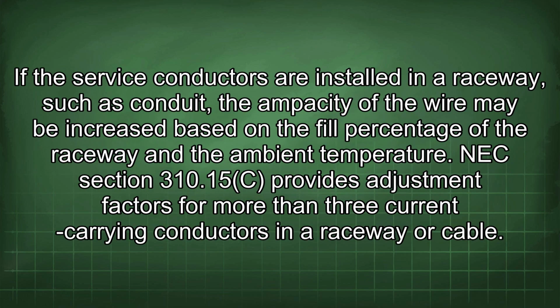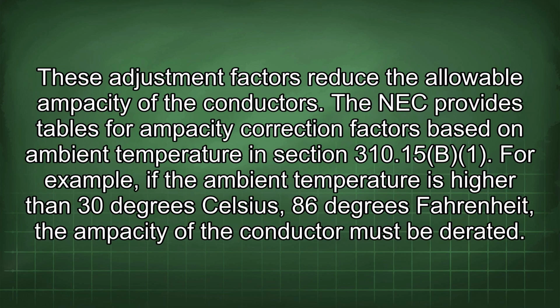If the service conductors are installed in a raceway, such as conduit, the ampacity of the wire may be adjusted based on the fill percentage of the raceway and the ambient temperature. NEC Section 310.15(C) provides adjustment factors for more than 3 current-carrying conductors in a raceway or cable. These adjustment factors reduce the allowable ampacity of the conductors. The NEC provides tables for ampacity correction factors based on ambient temperature in Section 310.15(B).